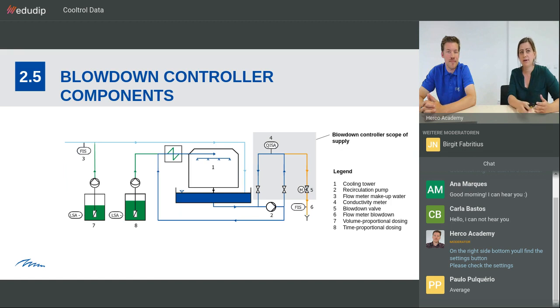You can see here in the gray square what is really the blowdown controller scope of supply. So the blowdown controller includes the control system and this part of the piping that is shown here in the gray square, which is the measurement of the conductivity and the blowdown valve.